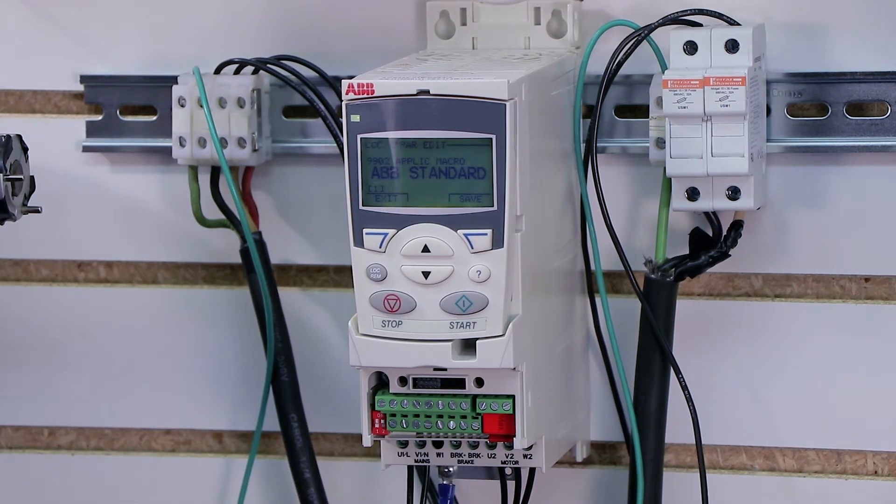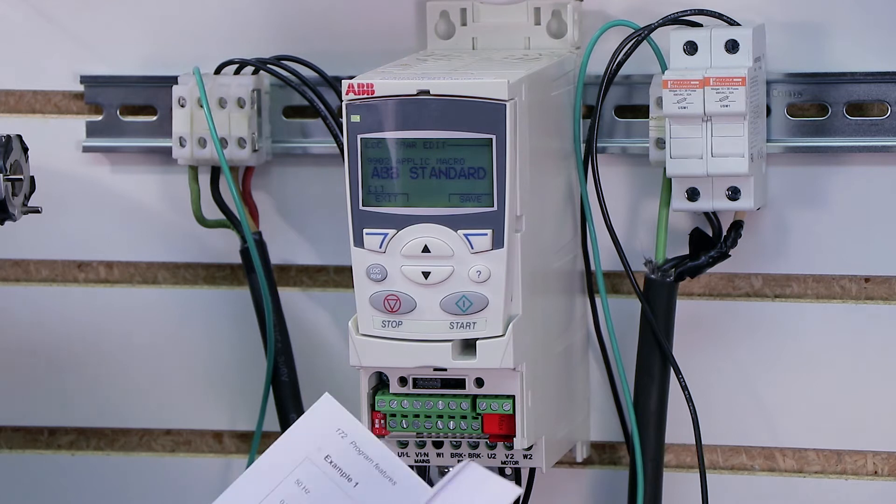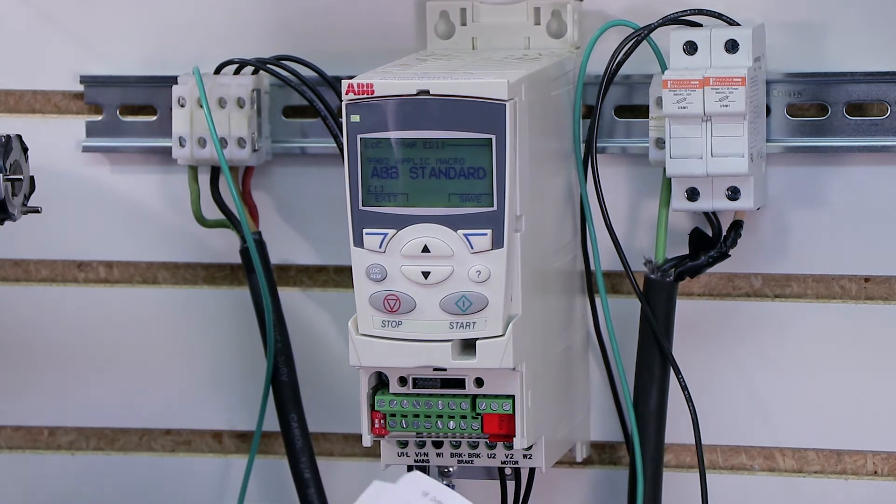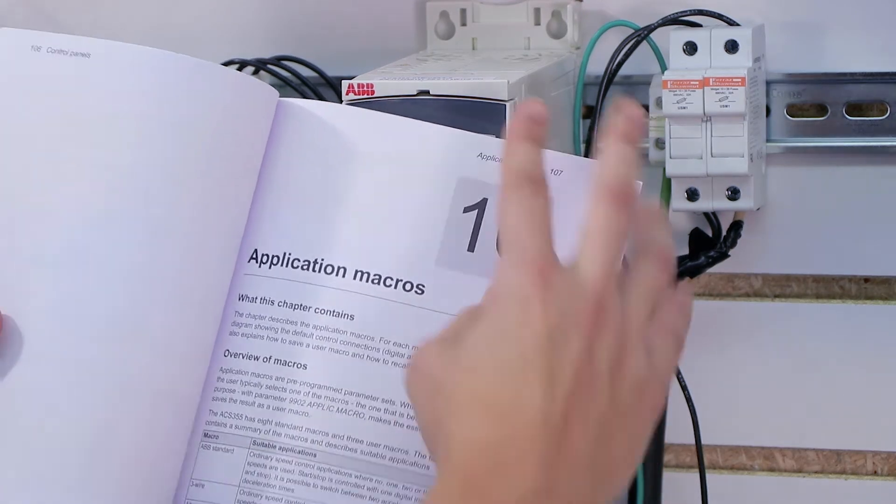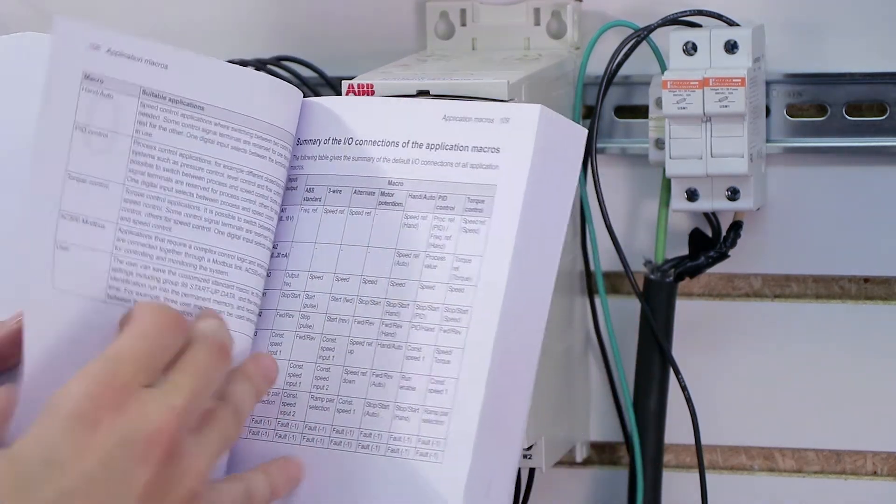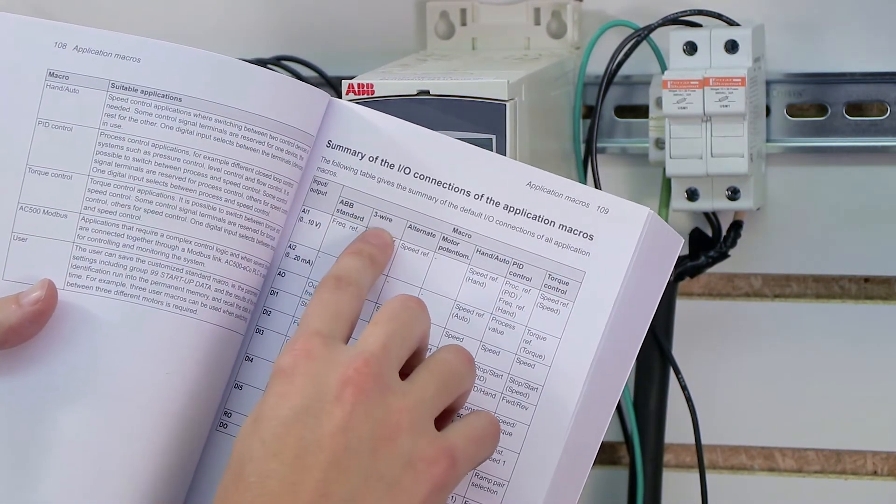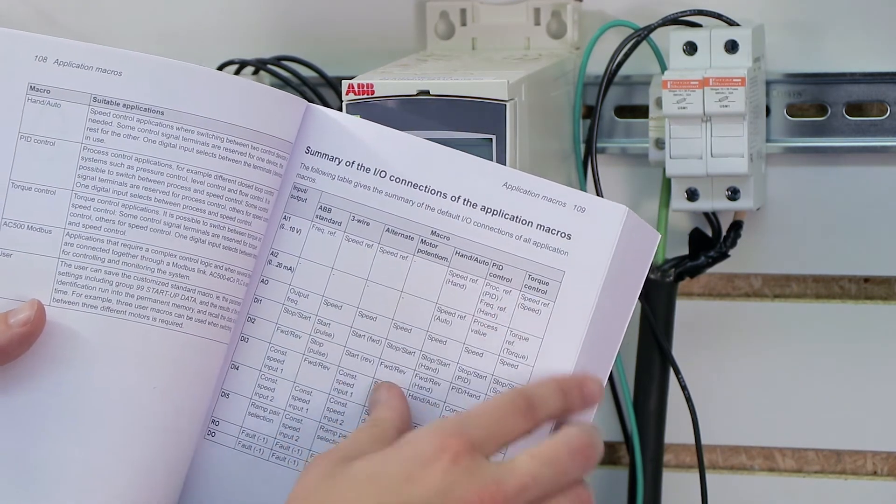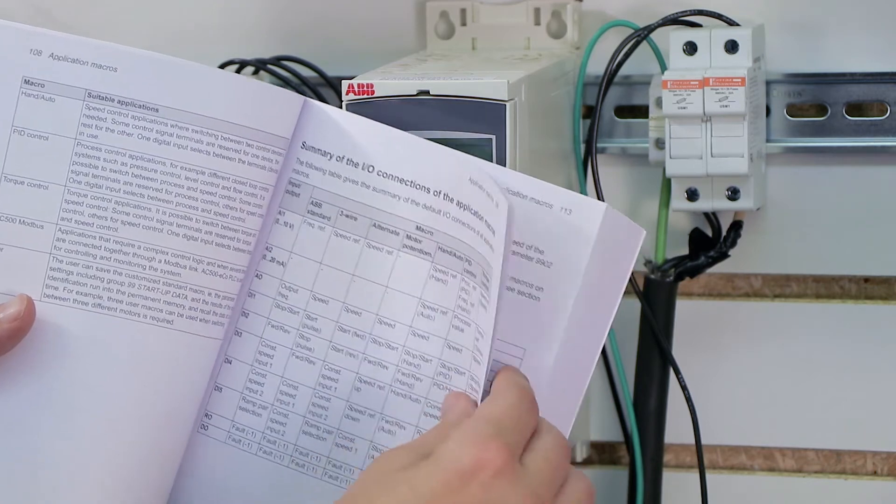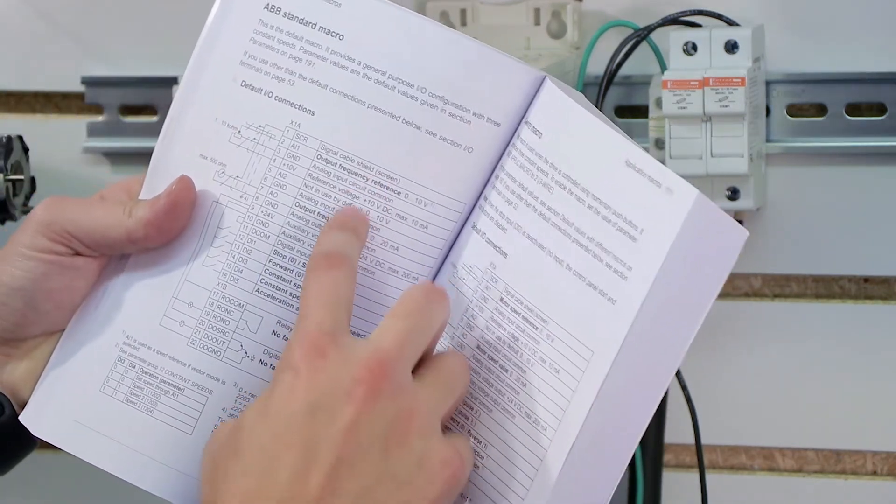Now macros are really cool. If you haven't had a chance to look in your manual yet, you can actually pull up the macro section, and the macro gives you a number of different, this is application macros in chapter 10. The macros give you basically a default configuration. So there's a standard, a three wire setup, an alternate setup, a motor potentiometer setup, a hand and auto setup. So these are like presets, they're pre-built-in presets for certain wiring setups and things like that.